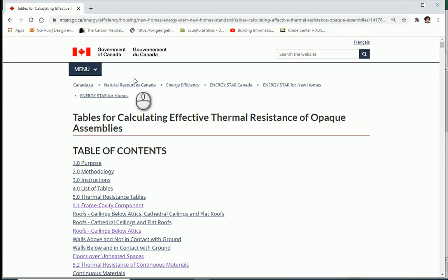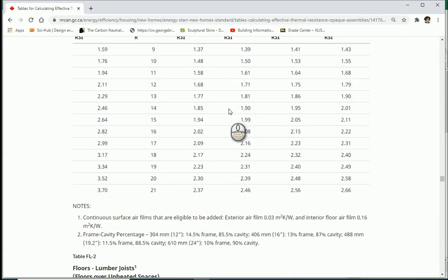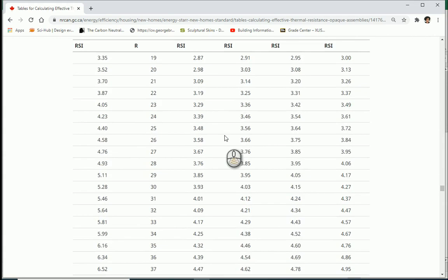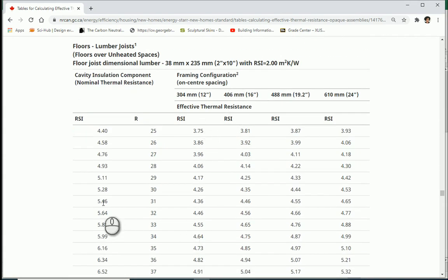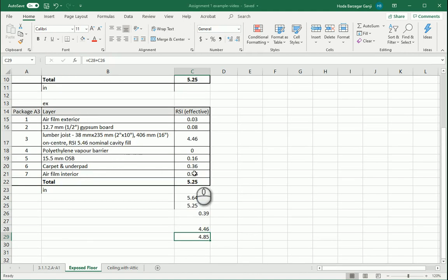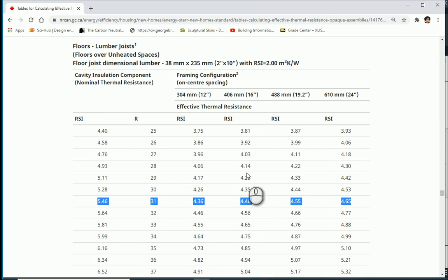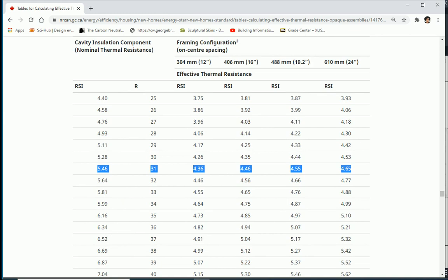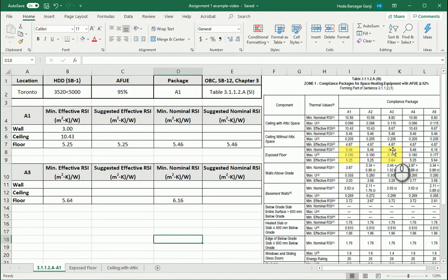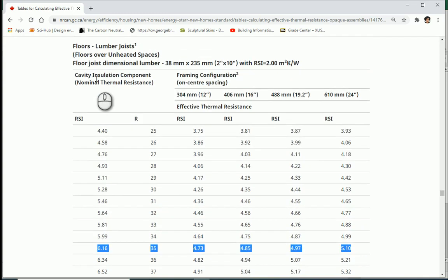Going back to the NRCan website under floors over unheated space, the previous value was a 2 by 4. I'll scroll down to 2 by 10. Before, 5.46 nominal gave us 4.46 effective at 16-inch spacing. Now the nominal should be 6.16, and I need to follow the row for 6.16 nominal RSI.